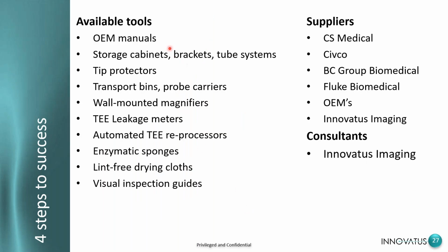So available tools, OEMs. The OEM makes these things, right? And so their manuals, especially when we look at the chemicals. When we look at TEE care, it is critical to reference the OEM manuals for proper cleaning and disinfection of their probes. I would love to get on these types of calls and say, hey, there is one cleaner, one disinfectant that is universal and works on every probe known to man and woman. I can't. It's because the different OEMs, they use different materials, they have different adhesives, different lenses, and so on. So there is no one universal cleaner disinfectant that is approved by the OEM that works on every probe. Storage cabinets, brackets, and tube systems, tip protectors.